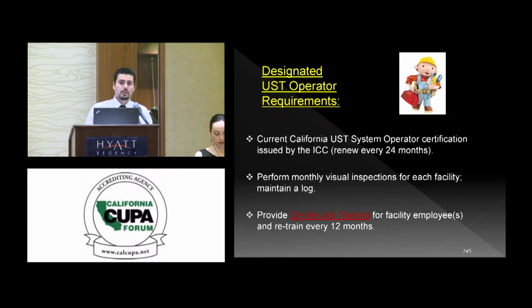And in some cases, if we're out there verifying the alarm history of the tapes, we can basically see just by checking the tapes when a cold start happens. So we go back on DO reports and see if they're doing their job right when that cold start happened. And we can then take it from there and verify what actions were taken, if they did pull a permit, if they called it in, or if they're just trying to play it off like they didn't know what happened.